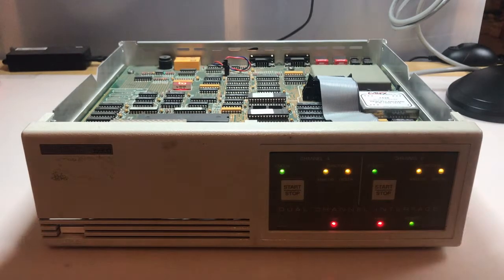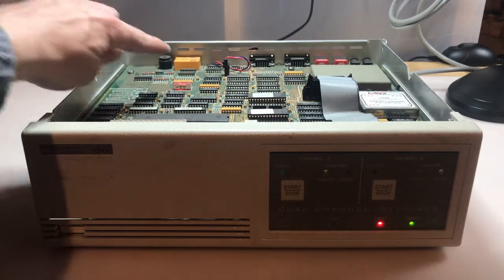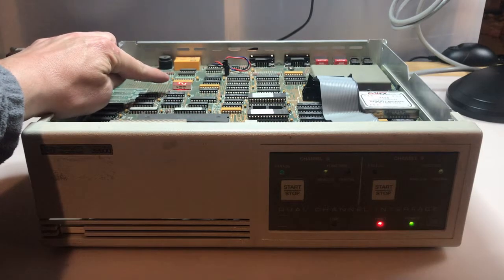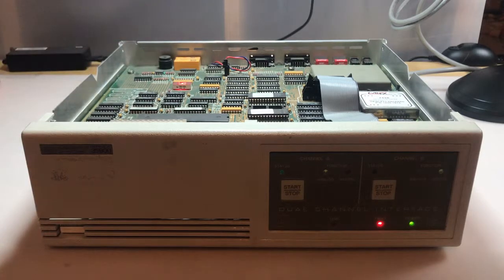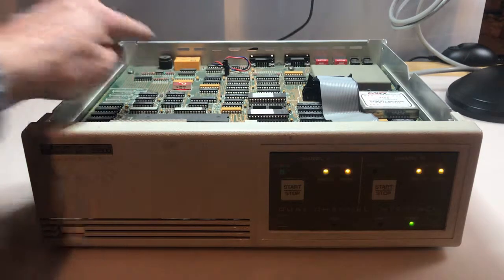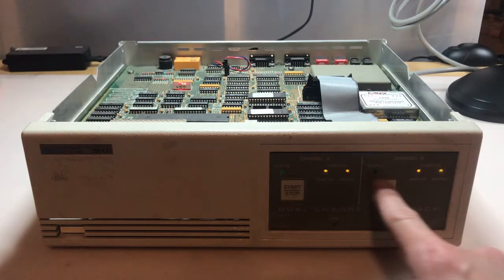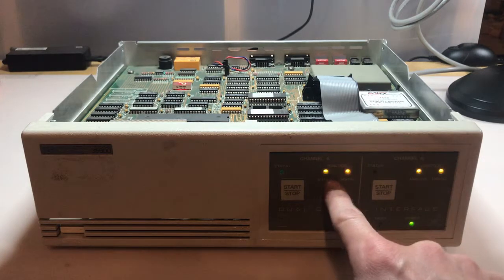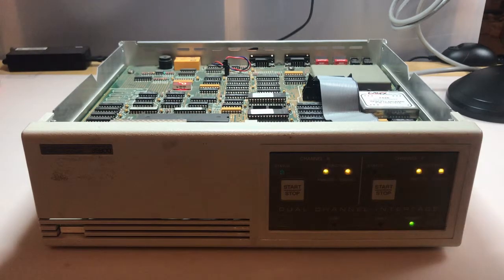When I power it up, watch the 7-segment display. It gets to 1, gets to 2. Before it would beep when it gets to 3, and now it gets to 3 and 4 just fine, and it continues on. So this is the self-test, and you can see it hits P for pass, and then now we just get these blinking lights here, and the fault light goes away. The blinking lights just indicate that we don't have any communication, obviously because I don't have anything hooked up. So now it is absolutely fixed. I feel 100% confident that this thing will work.